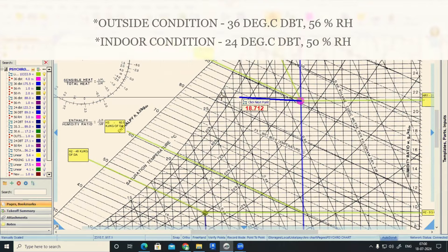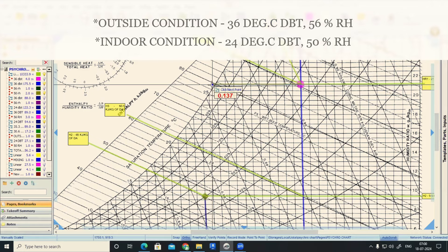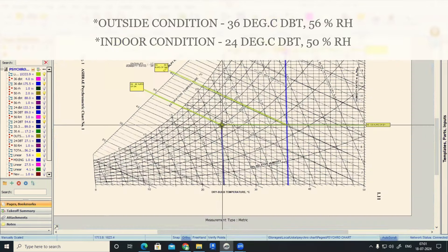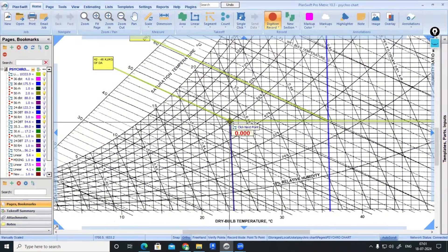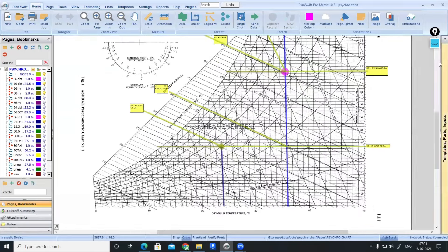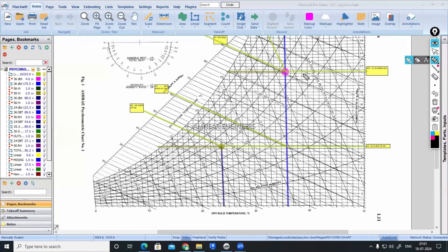What is the dew point of this state? The dew point of the indoor state will be at a certain point on the psychrometric chart. When will condensation start? When you are cooling the air, the condensation will not start immediately. The air will be entering into the cooling coil at 36 degrees Celsius dry bulb temperature and 56% relative humidity, and then it will be touching the cooling coil.